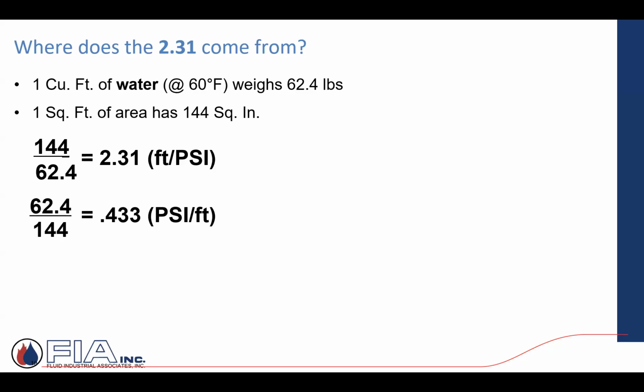If you did it the opposite and said, take my pounds, divide it by my 144 square inches, it's 0.43 pounds per foot. So I can go back and forth. I can convert from PSI to feet of head or feet of head back to PSI. That's all it's reflecting.